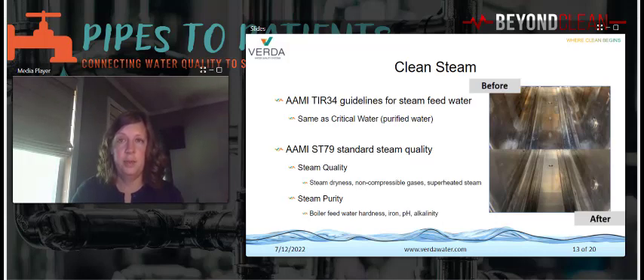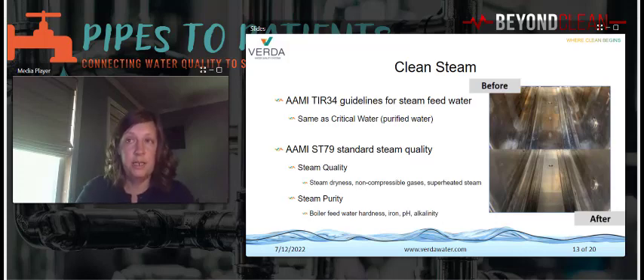And there's an argument that some manufacturers make that the boiler feed water that feeds SPS steam sterilizers doesn't need to be as stringent as TIR 34 outlines, and the boiler's instructions for use supersede any recommendation from AAMI. To that point, I'll assert the old adage, garbage in, garbage out, is an accurate assessment for steam sterilization. If you need to chemically treat your feed water and use steam filters to produce clean, dry steam, it nevertheless may not be sufficient to meet the needs of sterile processing services.